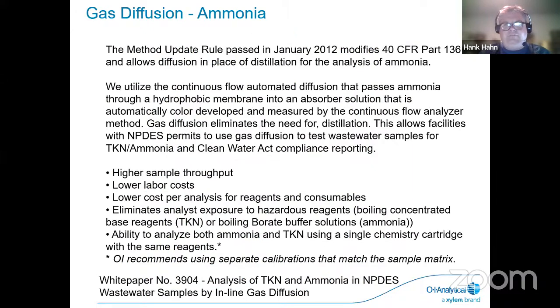We also, in the methods, include some of the important consumables per chemistry, so you can have part numbers and ID for some of the critical key components to replace over a period of time. So the gas diffusion method for ammonia was approved in January 2012, just as with the total cyanide, they were done together. And so we utilize continuous flow diffusion that passes the ammonia through that membrane into an absorber solution that is automatically color developed and measured by the continuous flow analyzer method.